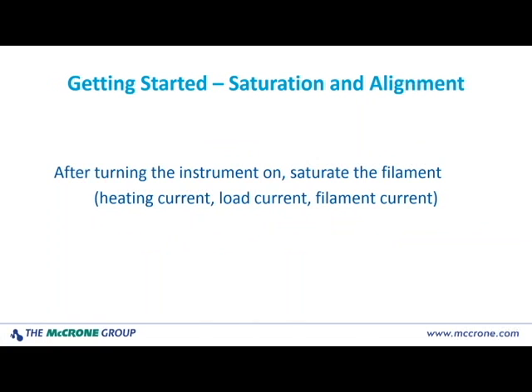Some people have said we don't saturate filaments — it's just on when we hit the button. We recommend that you go into your gun and actually turn the current that is in your filament down when you go to end of your session. When you bring it back up, you start at zero, and you're not shocking this filament. It's very delicate. It also forces you to recheck your saturation point, because as the filaments are used, they wear. Therefore, your saturation point may change over time, so your image is going to degrade on you just by turning it on and off. You want to find what's called the heating current, load current, or filament current setting — the terms are synonymous. The same manufacturer will switch between instruments; they may use the abbreviation, or maybe even the acronym like load current might be designated as LC.